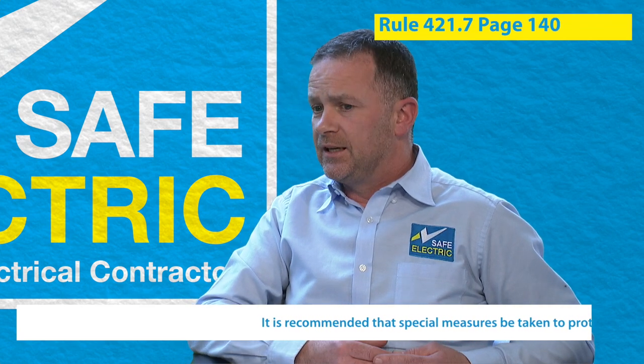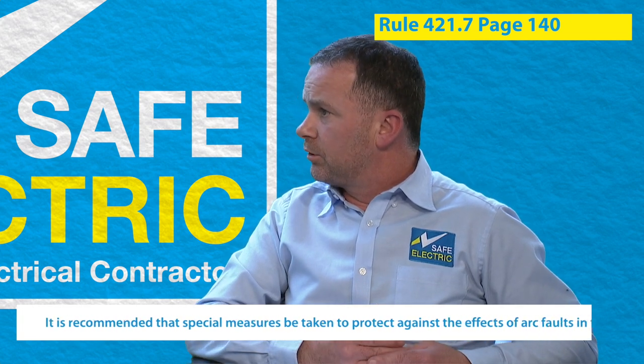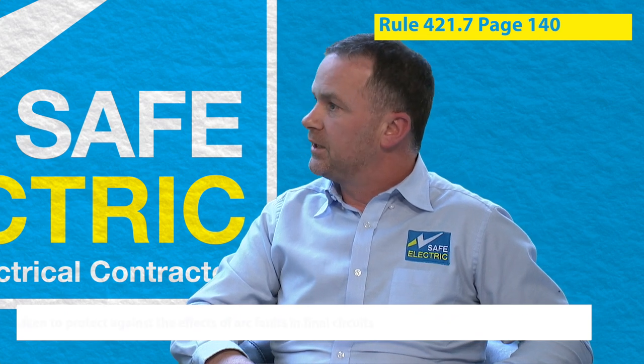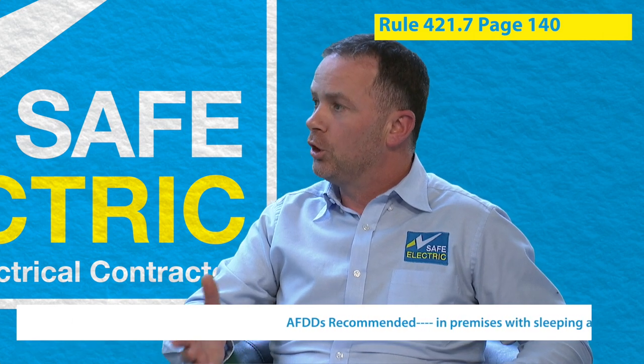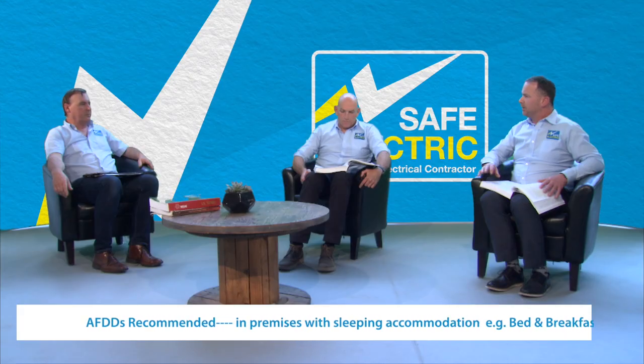What is arc fault detection? In a distribution board, whether it's commercial, industrial, agricultural, today we have two typical types of protection devices. One would be short circuit or overload protection done by an MCB or a fuse, and then we have an RCD, residual current device, which is looking for earth faults. But if we had a loose connection, and that could be in a trailing socket, it could be the back of a switch, it could be in a junction box in the attic, that's not going to be picked up by either of these two devices. Yeah, and this is a fire hazard.